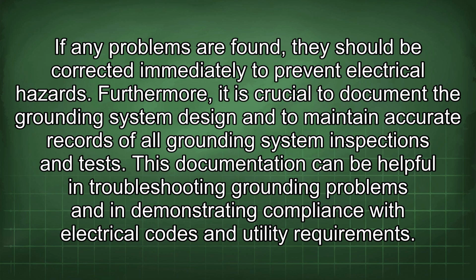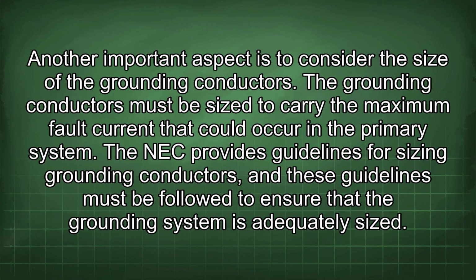Furthermore, it is crucial to document the grounding system design and to maintain accurate records of all grounding system inspections and tests. This documentation can be helpful in troubleshooting grounding problems and in demonstrating compliance with electrical codes and utility requirements. Another important aspect is to consider the size of the grounding conductors. The grounding conductors must be sized to carry the maximum fault current that could occur in the primary system. The NEC provides guidelines for sizing grounding conductors, and these guidelines must be followed to ensure that the grounding system is adequately sized.